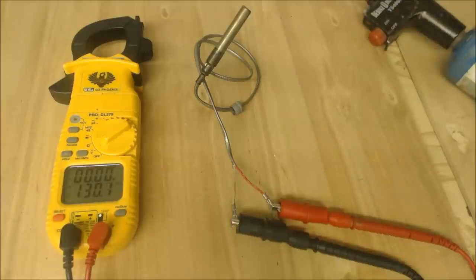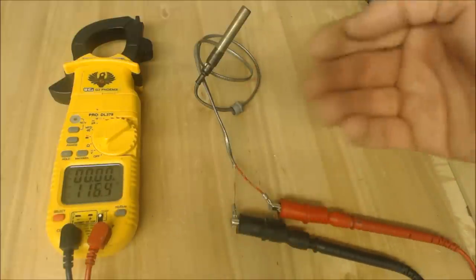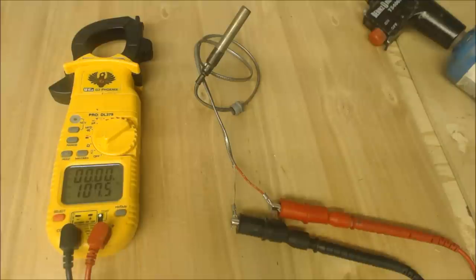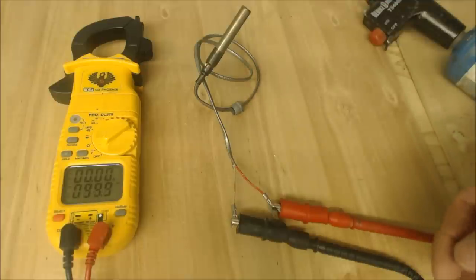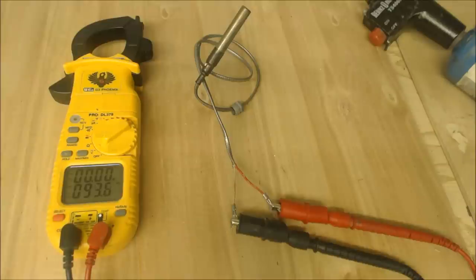So you may want to check on that manufacturer just to see. But if you were at like 130 millivolts DC or 120 somewhere around here, it's not going to be enough to open the gas valve in order for the gas to flow through.